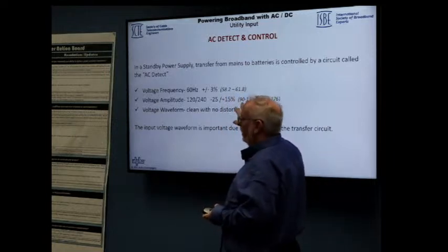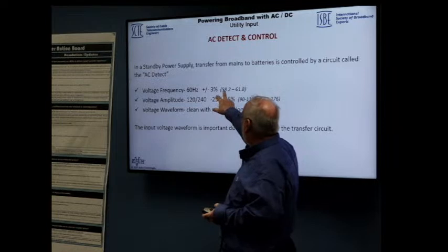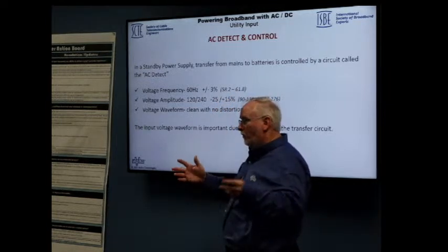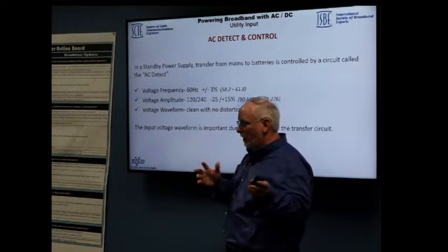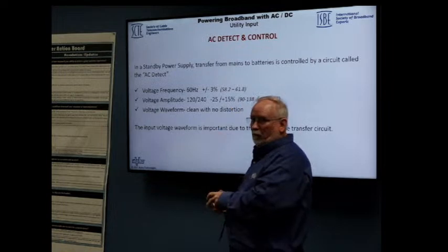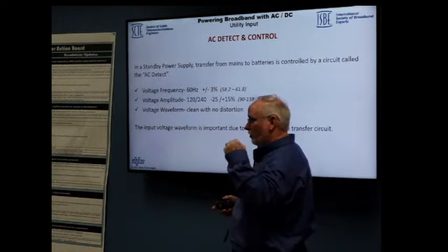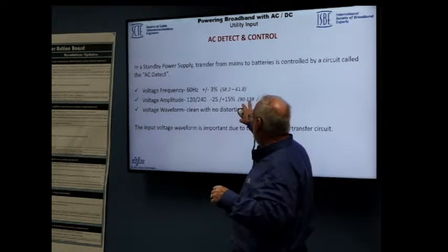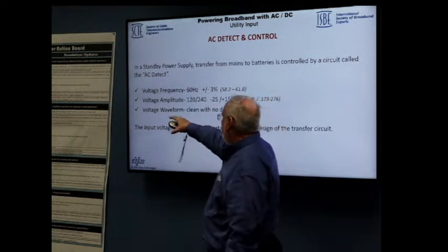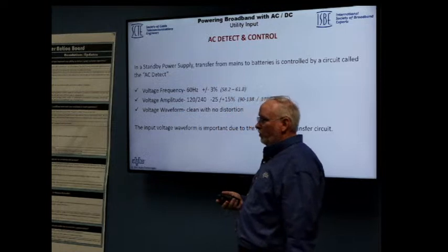As long as your power supply, your 120 volt battery, stays between these numbers, it'll stay online. Now, our field devices don't really care about what the AC frequency is, so that's not a big deal. And they'll operate through this, and the power supplies actually are a tapped transformer, so it'll regulate the output, and the ferro also helps with that regulation. And then make sure there's no distortion in the waveform.